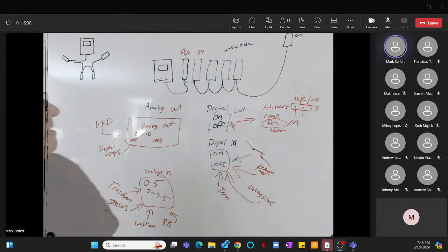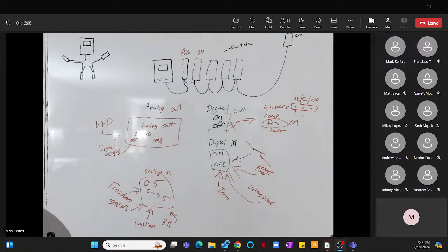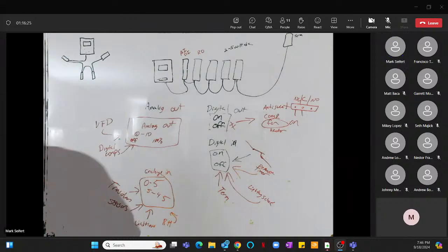You don't want to freeze up your entire meat counter, and it happens quick. It's better to have it alarm and give somebody time. It also won't ice up nearly as bad. You got a plus 20-degree coil system and it's running at minus 10 until you get there. Coils are going to be iced up bad. But if you got a plus 20-degree system and it fails and it runs at plus 25, well, you have a lot better chance of not having everything iced over solid. So that's where half of them, and every rack we make at the shop, it's the same way. Half wired normally closed, half wired normally open. It's a safety. Gives you some time.